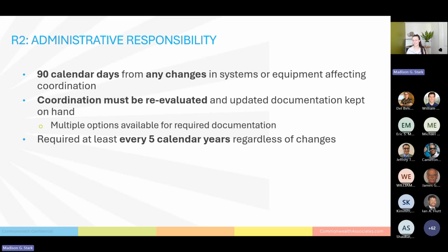The second half of this is the administrative responsibility. The way the regulation is written, within 90 calendar days of any change in these protection or limiting systems or generator capabilities, you have to redo this coordination study and have updated documentation. Even if you don't change anything, you still have to have updated documentation at least every 5 calendar years. So even if you don't change a single thing on your entire site, you still have to do a PRC 19 coordination study every 5 years and keep that documentation on hand.